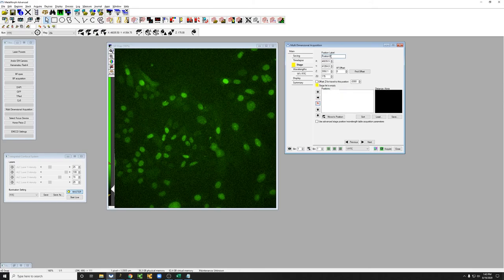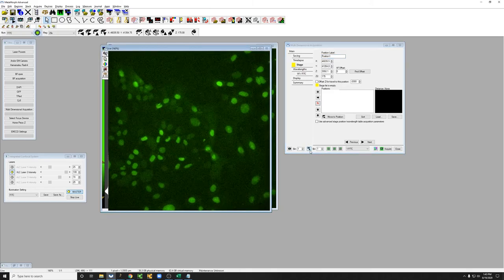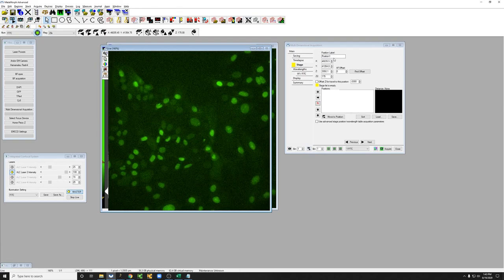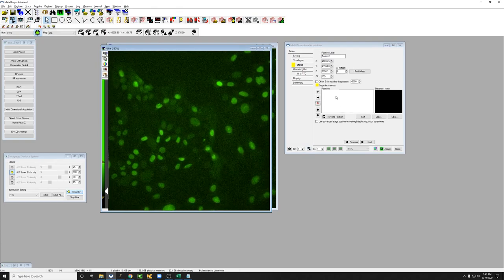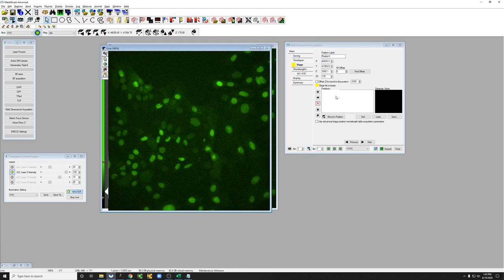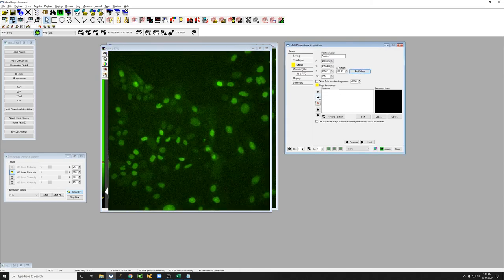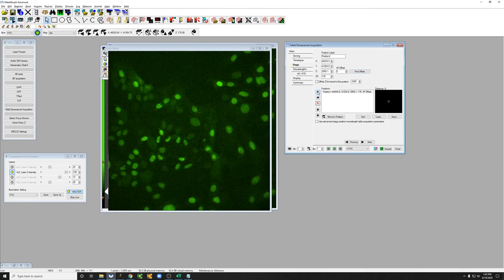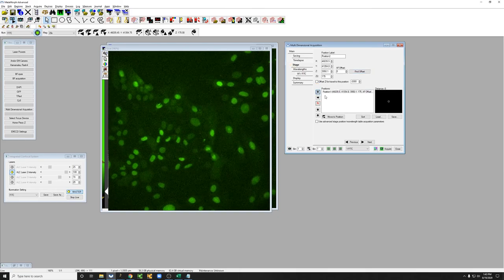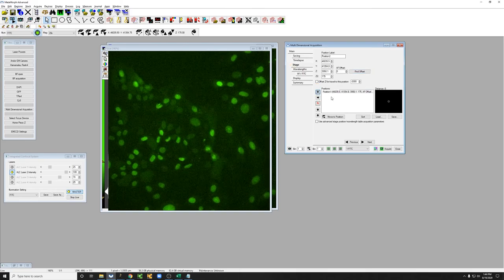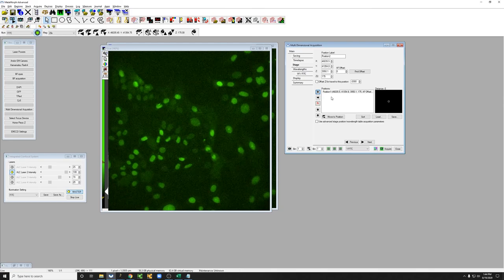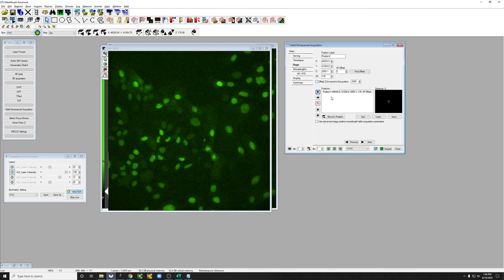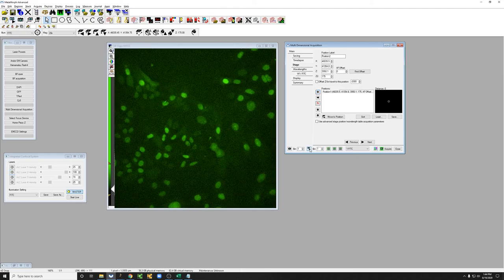And now we're going to add a position where we are if we are in focus. I'm going to go to live, that seems like we're in focus. So then before we add that position for it to, for the autofocus to be read, we're going to click on find offset and then add the position. If we don't do that then the autofocus won't know where to go and so it won't work during live cell imaging. So let me turn off the live.